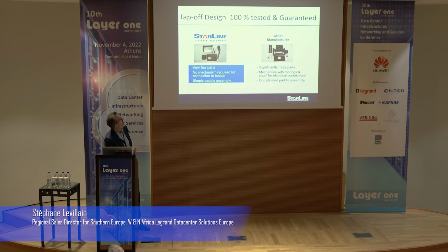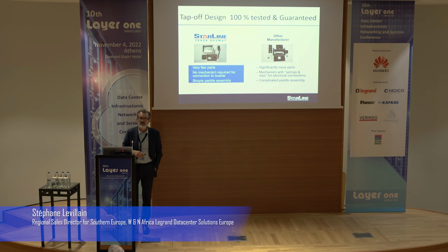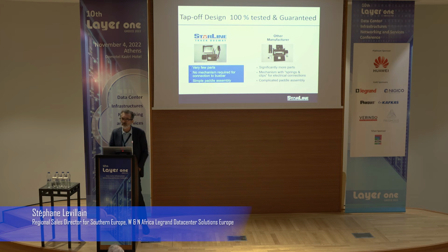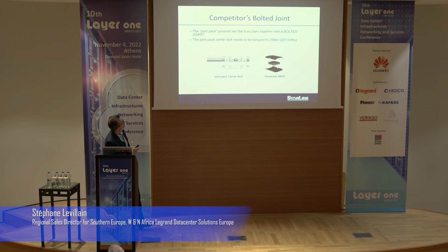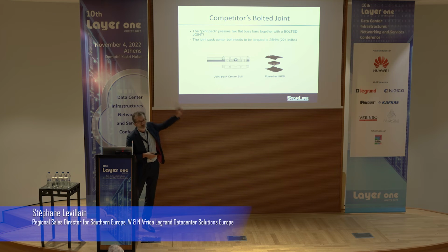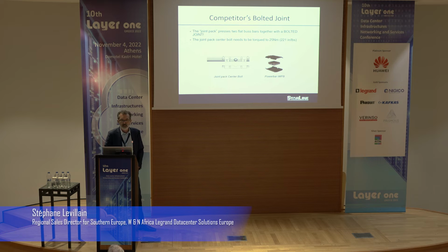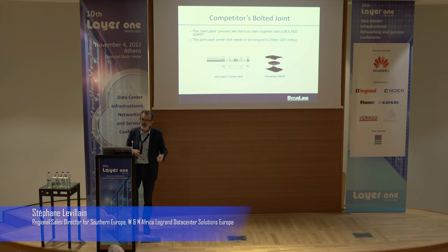When it comes to reliability, all the tap-offs that leave the Starline factory are fully tested, 100% tested and guaranteed. As I said before, we have very few parts, no moving parts, no washers, screws, and compared to others, that makes a big difference in terms of reliability. For instance, some others are using joint kits with nuts and bolts. Clearly, this has to be torqued, for instance this one at 25 Newton meter. And if you have to retighten, you need to switch off, which is a big problem for the data center operation manager.